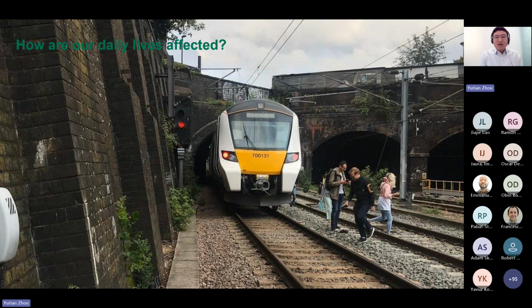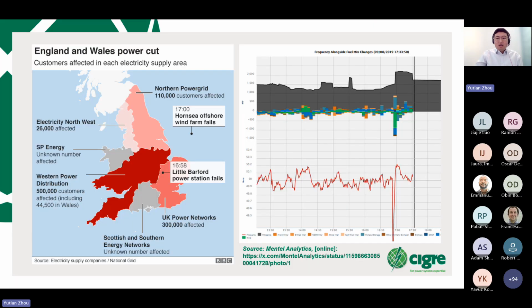And the screen only captures one of the occasions when passengers had to be evacuated from the trains and walk along the tracks to basically leave the train. So diving into a little bit more detail, how did everything happen? As I said, when the lightning struck, it caused a fault on the 400 kV lines, and this was nothing extraordinary and was rectified by the protection systems within 80 milliseconds.